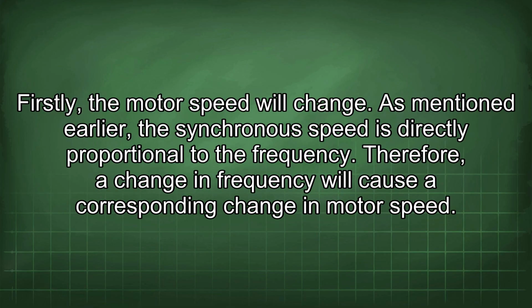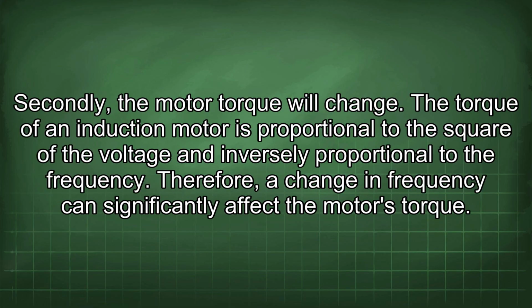Firstly, the motor speed will change. As mentioned earlier, the synchronous speed is directly proportional to the frequency. Therefore, a change in frequency will cause a corresponding change in motor speed. Secondly, the motor torque will change. The torque of an induction motor is proportional to the square of the voltage and inversely proportional to the frequency. Therefore, a change in frequency can significantly affect the motor's torque.